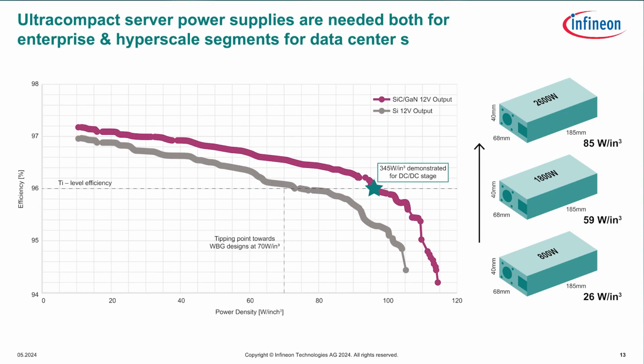So if we now look into solutions based on silicon, we are seeing that at around 70 watt per cubic inch, they are reaching a tipping point where silicon-based designs no longer can meet both titanium level efficiency as well as the required power density. So if you move beyond 70 watt per cubic inch in terms of power density, we see a clear value of wide-bandgap devices, typically silicon carbide in the PFC stage and the totem pole, and gallium nitride in the LLC.